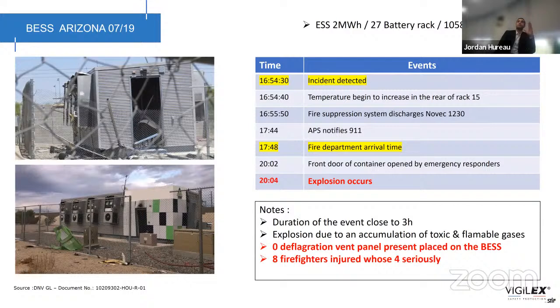Between the first detection of the incident, at nearly 5 p.m., and the explosion, nearly 3 hours passed. At around 5 p.m. the incident was detected, so there was some warning for the firemen to come. They arrived about an hour later, and for 2 hours they tried to evaluate and see what they could do to stop the fire from going on, because the fire suppression had been discharged earlier. So 2 hours after their arrival, firemen decided to open the front door.